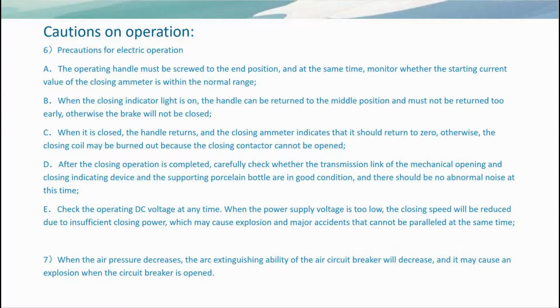D. After the closing operation is completed, carefully check whether the transmission link of the mechanical opening and closing indicating device and the supporting porcelain bottle are in good condition, and there should be no abnormal noise at this time. Check the operating DC voltage at any time. When the power supply voltage is too low, the closing speed will be reduced due to insufficient closing power, which may cause explosion and major accidents that cannot be paralleled at the same time. 7. When the air pressure decreases, the arc extinguishing ability of the air circuit breaker will decrease, and it may cause an explosion when the circuit breaker is opened.